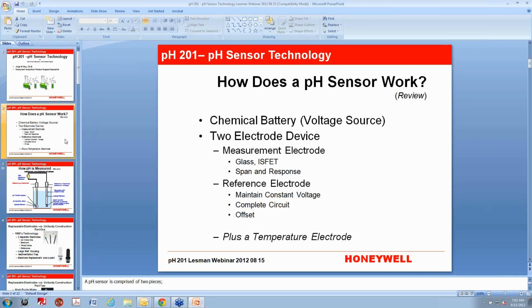The reference electrode is there to maintain a constant voltage to be compared to the changing voltage of the measuring electrode, and it completes the electrical circuit. Without the reference electrode, you can't have a complete circuit. And it's responsible for offset. So if you put your pH sensor in a 4 buffer and a 7 buffer, and it measures 4.5 and 7.5, that means it has a perfect span of 3 pH, but has an offset of half a pH, and that would be related to the health of the reference electrode.